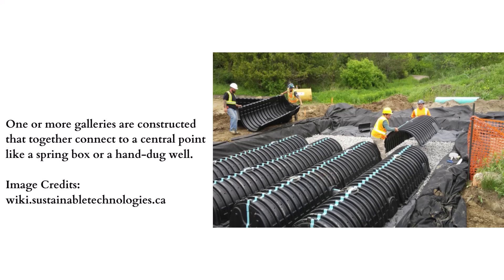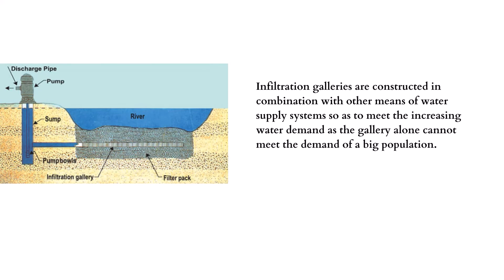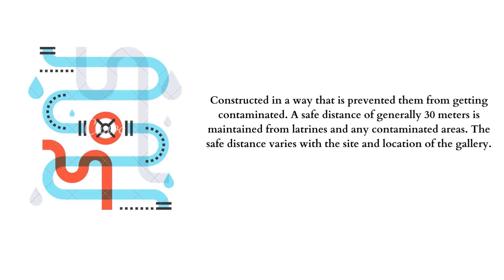One or more galleries can be constructed together and connected to a central point like a spring box or a hand-dug well to achieve a higher yield. Infiltration galleries are also constructed in combination with other water supply systems to meet increasing water demand, since a single gallery cannot serve a larger population. They are constructed in a way that prevents contamination, maintaining a safe distance of generally 30 meters from latrines and any contaminated areas.